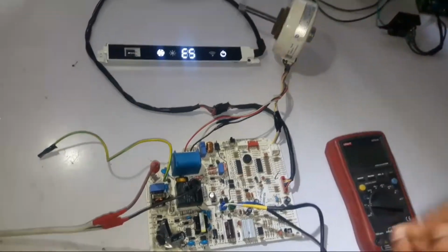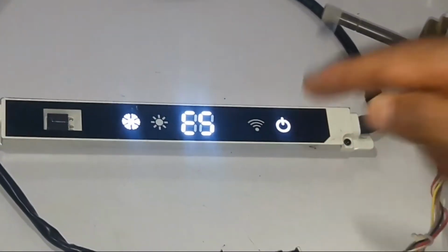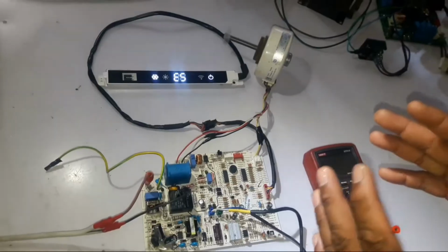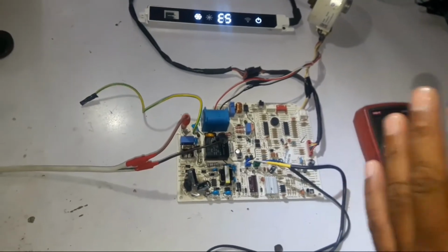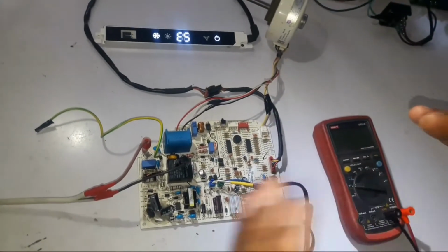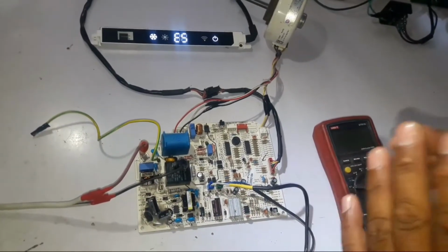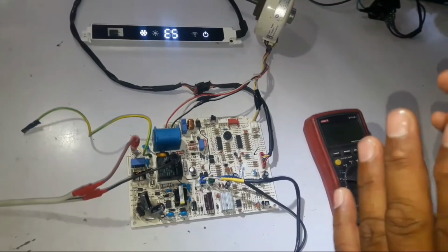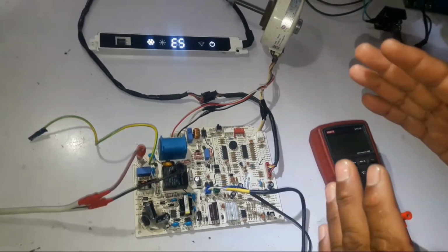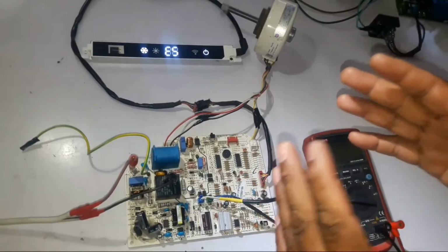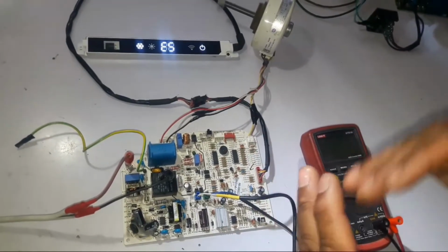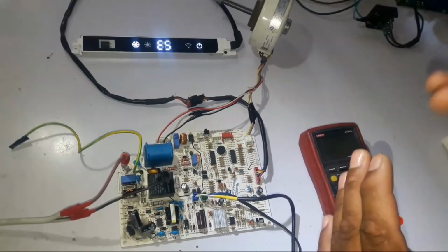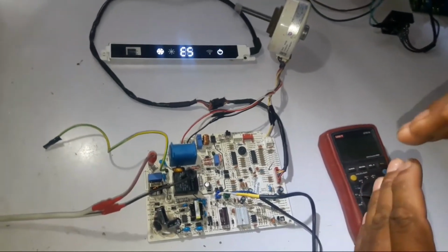Now, you can see that the E5 error has appeared on the unit display. The E5 error indicates a communication failure between the indoor and outdoor units due to a disconnection. This error can occur in 2 or 3 different situations. 1. If the outdoor circuit is faulty, the E5 error may appear. 2. If there is a problem with the connection between the indoor and outdoor units, such as a damaged or loose line, neutral, or signal wire, the error can also occur. 3. A faulty indoor circuit can also be responsible for this issue. To fix this, check and repair the faulty components. Once the issue is resolved, the E5 error will disappear.